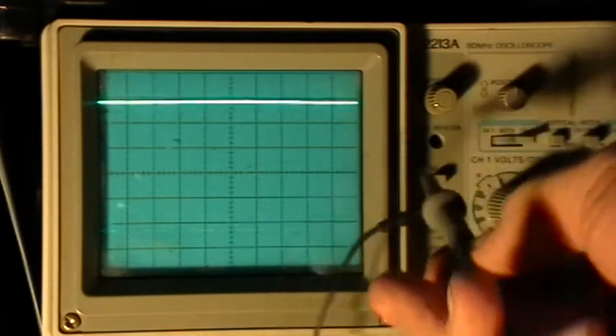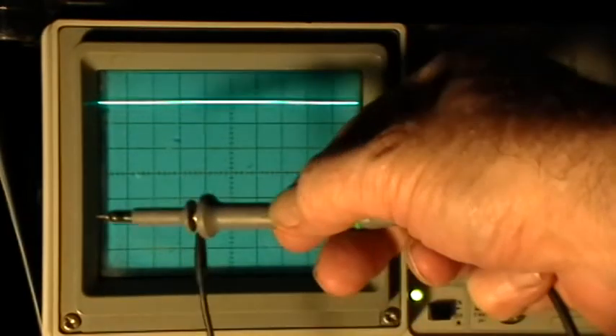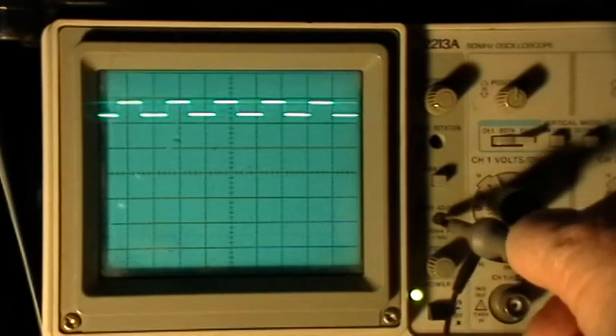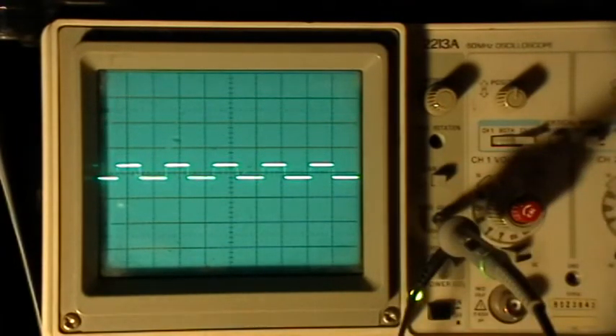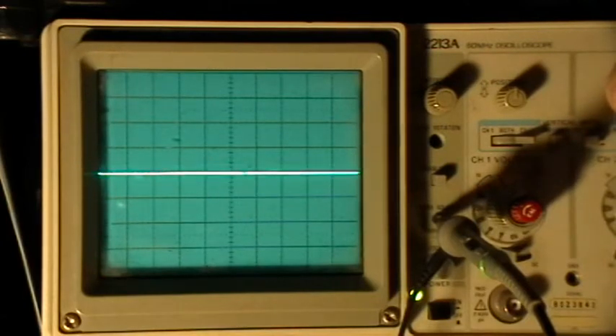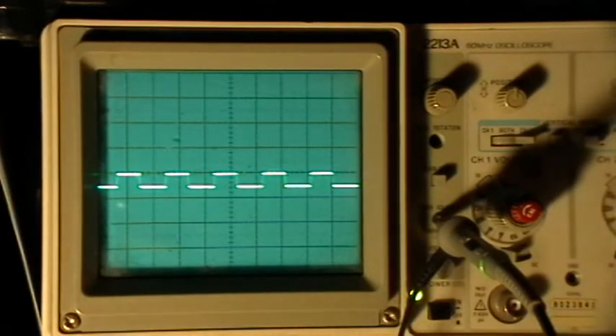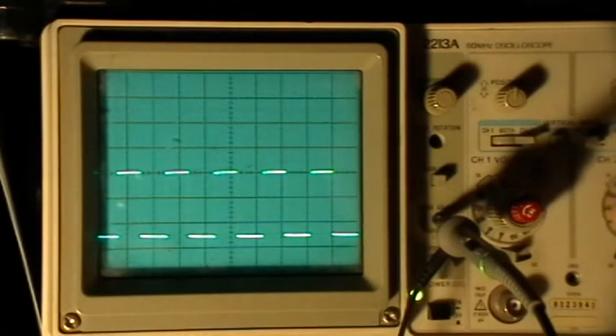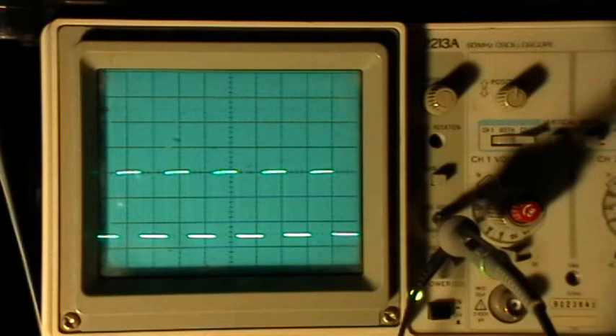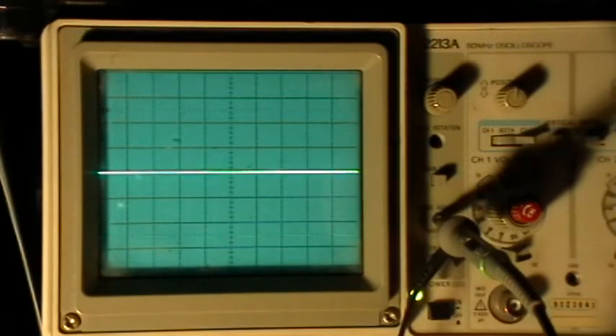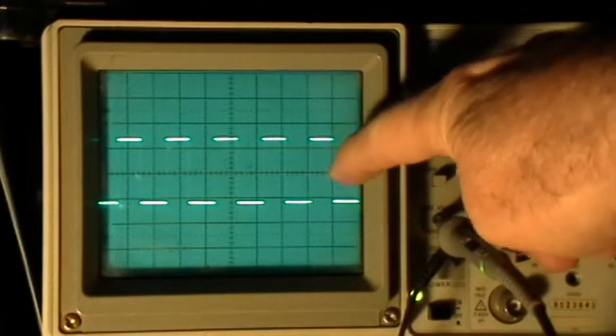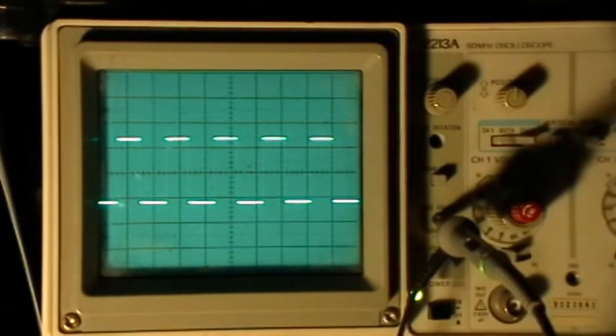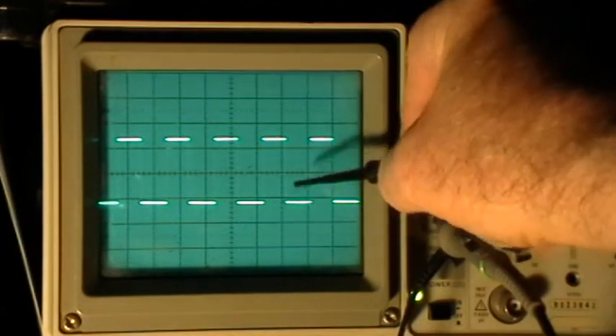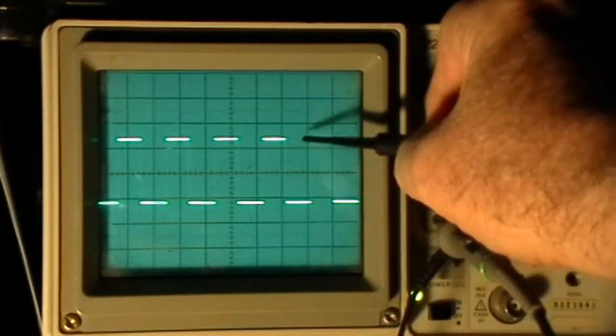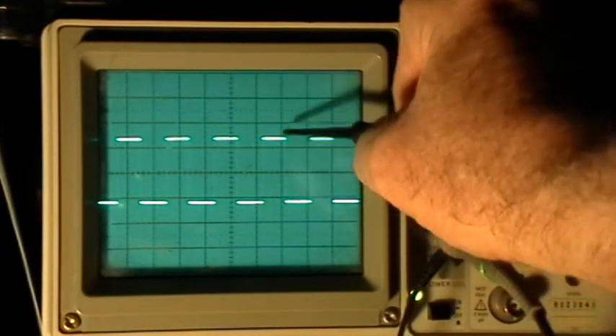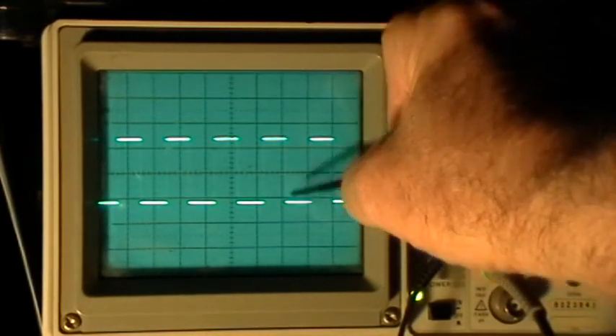Okay, so most of the time when you do measurements with the scope probe, you want to use 10x attenuation. You want to have that compensation capacitor adjusted properly, and you'll be using DC coupling to get the best looking trace on the screen. With AC coupling, the average of that trace moves to the center graticule line, but you have to be careful about the symmetry, the time symmetry of the traces. Otherwise you might be thrown off by the fact that the amplitudes look a little bit different, top and bottom.